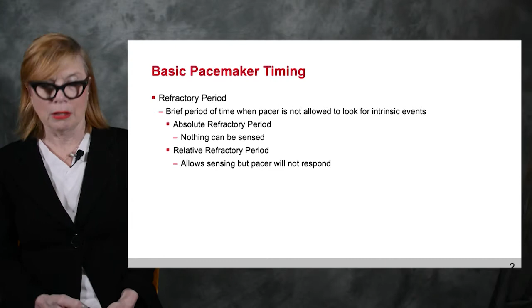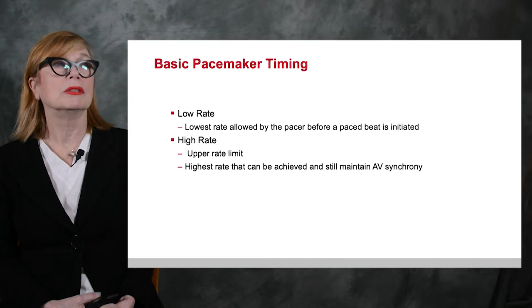Okay, so basic pacemaker timing that gets set. We set the low rate. That low rate means anything lower than that, the pacemaker is going to fire. And then we set the high rate, that upper rate limit. So that highest rate that can be achieved to still maintain AV synchrony. Beyond that, we will not be able to maintain an AV synchrony.